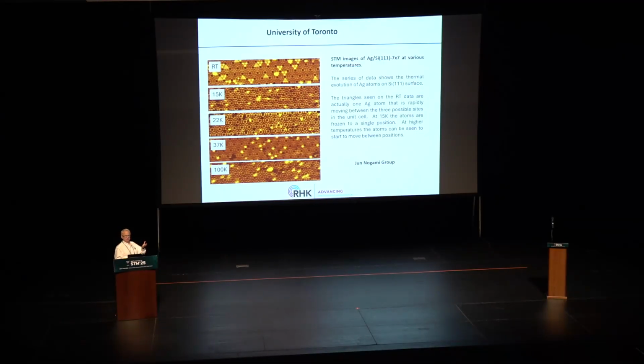As for drift, there's almost no drift at any temperature because the head, the probe, the sample, the body, and the inner shield are all at the same temperature. We're raising the temperature of the cold finger, so everything moves. There are no thermal gradients once it's reached equilibrium.